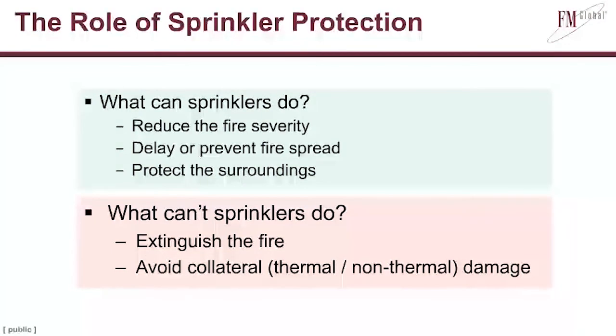Now, I've heard in the past when I presented on this that sometimes these results can lead people to think that there's no value in sprinkler protection, and I want to make sure I'm being absolutely clear here. There is a very strong value in sprinkler protection, but it's important to understand the role of sprinkler protection here. So, what can sprinklers do? They can reduce the fire severity. We've seen that for 2 different chemistries. They can delay or prevent fire spread from one rack to its neighbor, and they can protect the surroundings.